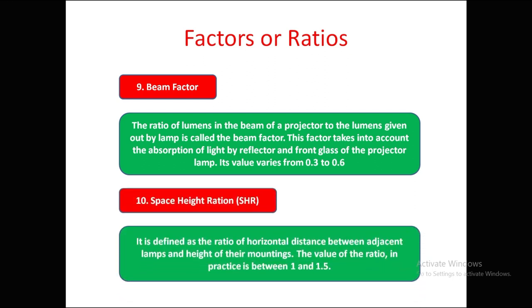Space-height ratio is defined as the ratio of horizontal distance between adjacent lamps to the height of the mounting. In practice, this ratio is between 1 and 1.5.